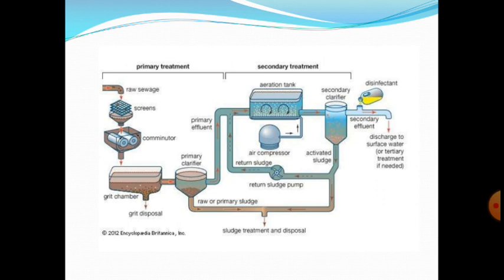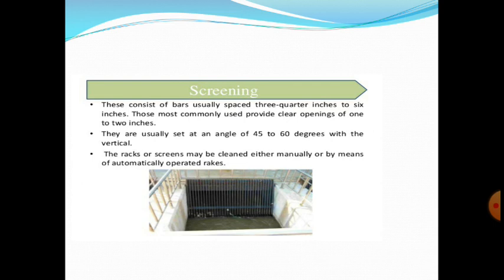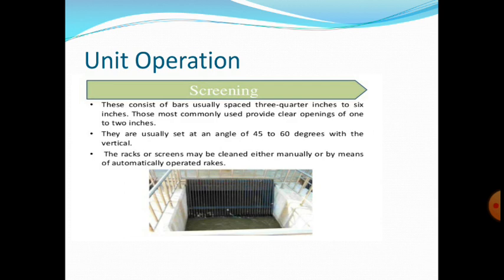In primary treatment, the sewage enters the screens, where big particles are removed. Screening is a unit operation done to remove large suspended and floating solids from wastewater, in order to protect pumps, pipes, and walls from clogging and damage. Examples include rags and pieces of cloth from cotton textile waste, fine fibers from woolen mills, spent tan bark from vegetable tanning processes.